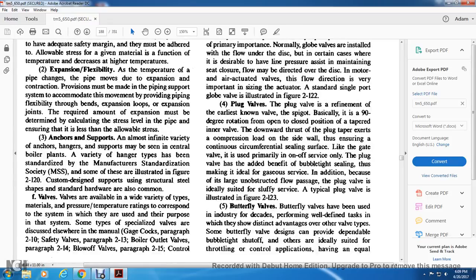Plug valve. The plug valve is a refinement of the earliest known valve, the spigot. Basically it is a 90-degree rotation, open and closed position, tapered internal valve. The downward thrust of the tapered plug exerts a compression load on the sidewall, creating a continuous circumferential sealing surface. Like the gate valve, it is used for primary on-off service. The plug valve has the added benefit of bubble-tight sealing, making it ideal for gaseous service. In addition, because of its large unobstructed flow passages, the plug valve is ideally suited for slurry service. A typical plug valve is illustrated in Figure 2-123.